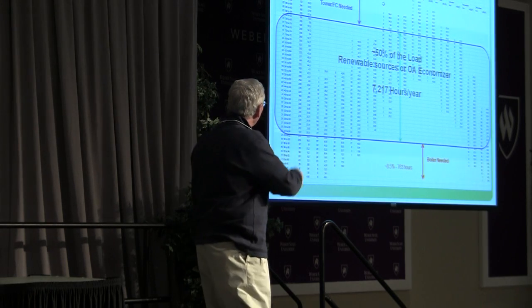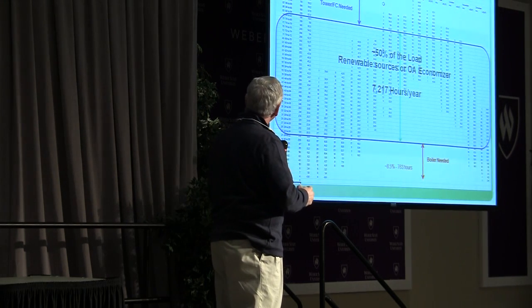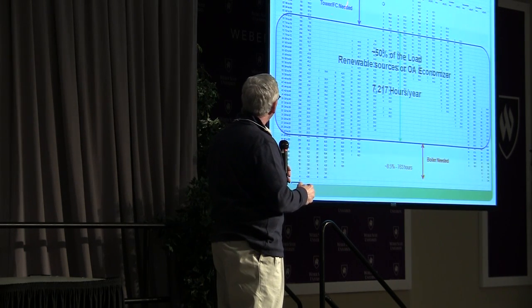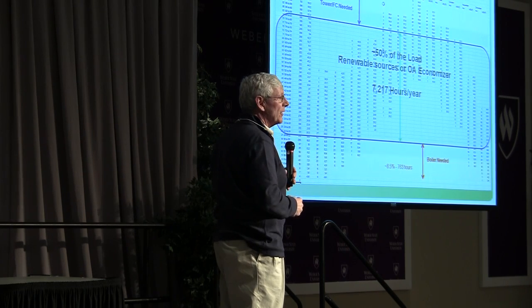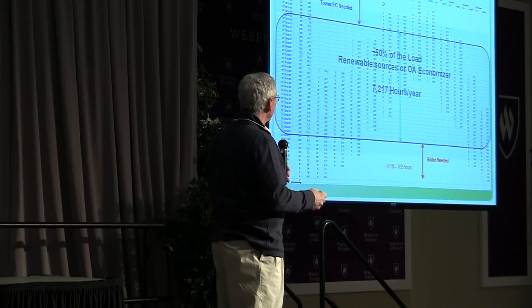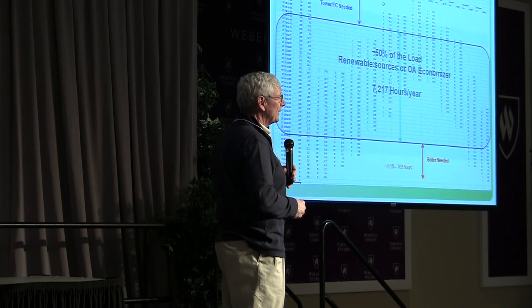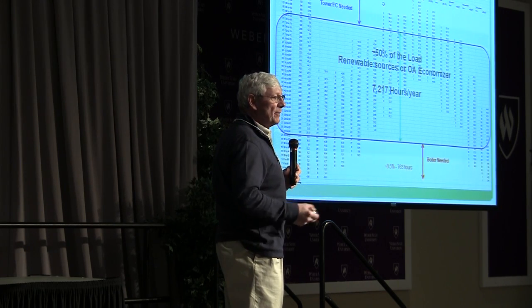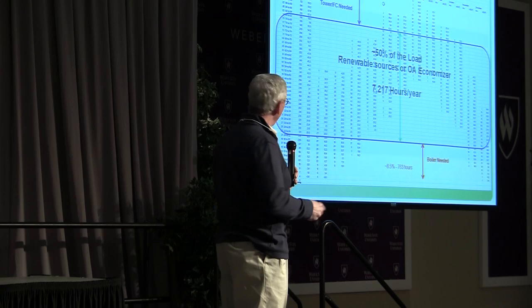And then we got to add a little bit. In this particular example, we're adding a tower in the summertime for about 760 hours. We've got a system I'll show you later, down in Las Vegas. The total runtime on the coolers for the year is about 400 hours.